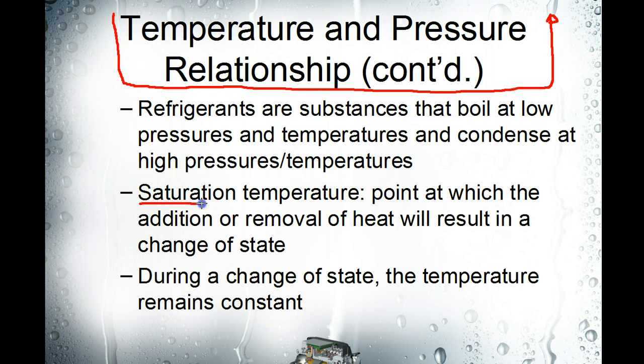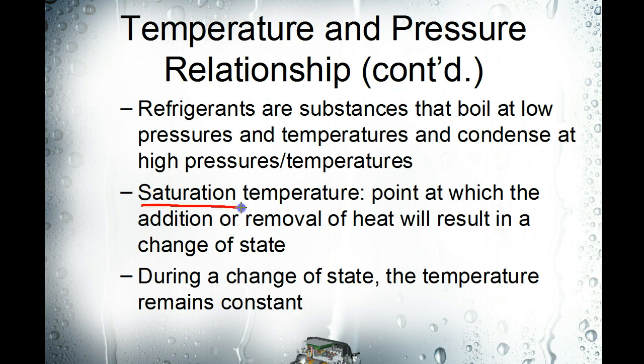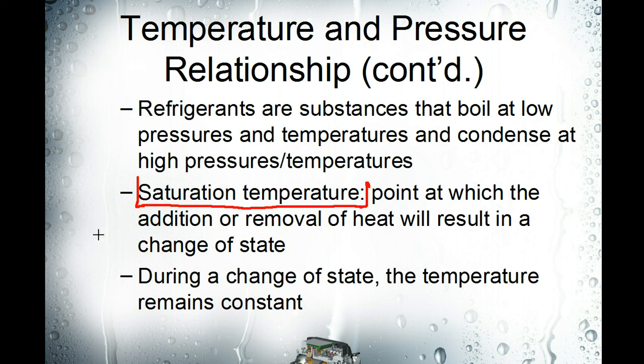This is a very important concept to understand in refrigeration — that's saturation temperature. The pressure-temperature relationship of refrigerants is always at the saturation temperature. The saturation temperature is where we have liquid and vapor together in a container. There'll be liquid on the bottom and vapor on the top. And if we take away just one degree of heat energy, it's going to start to change the state of that vapor back to liquid.